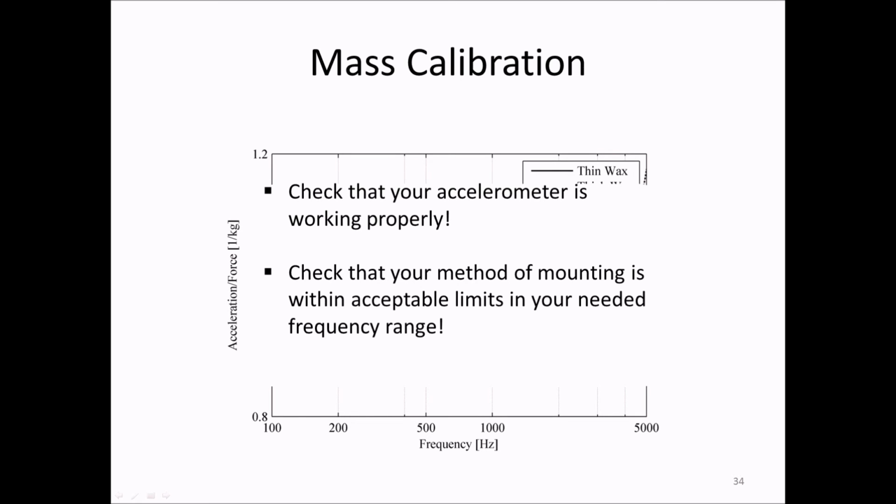You can also check that your method of mounting is within acceptable limits in your needed frequency range. And you can use it for actual calibration. This is recommended for the most accurate scaling of impact test measurements.